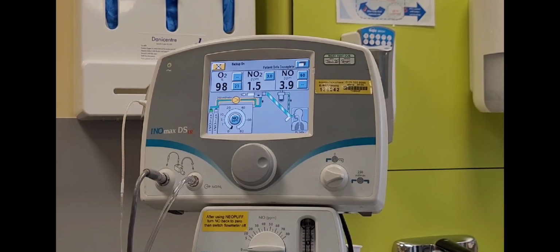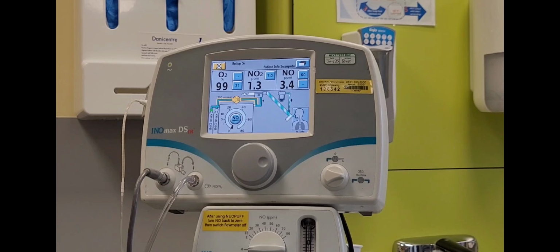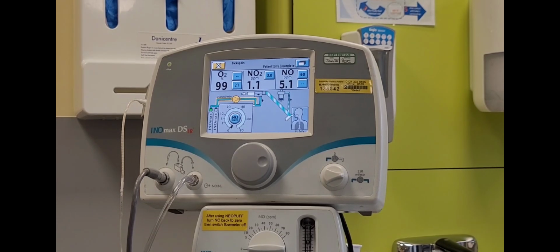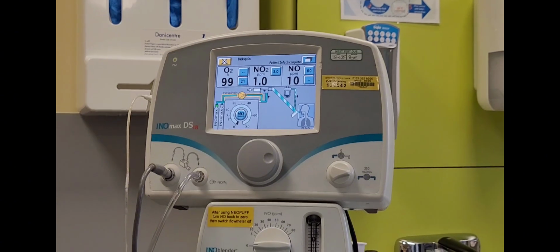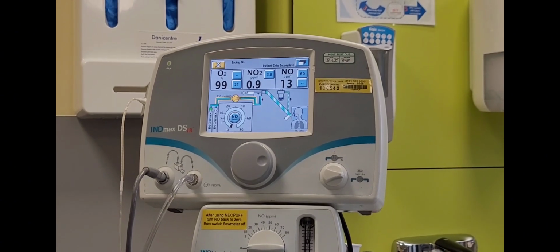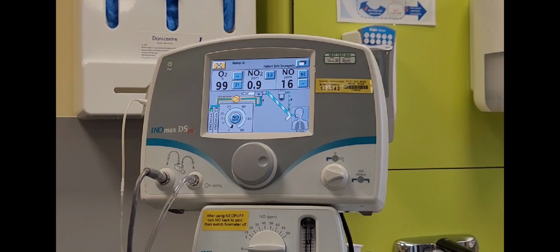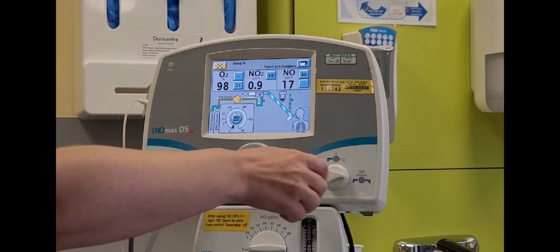You are looking for values here that are nitrogen dioxide equal or less than 1.5 parts per million, and NO between 14 and 25. This can take a few minutes. Once achieved, turn the backup delivery off.